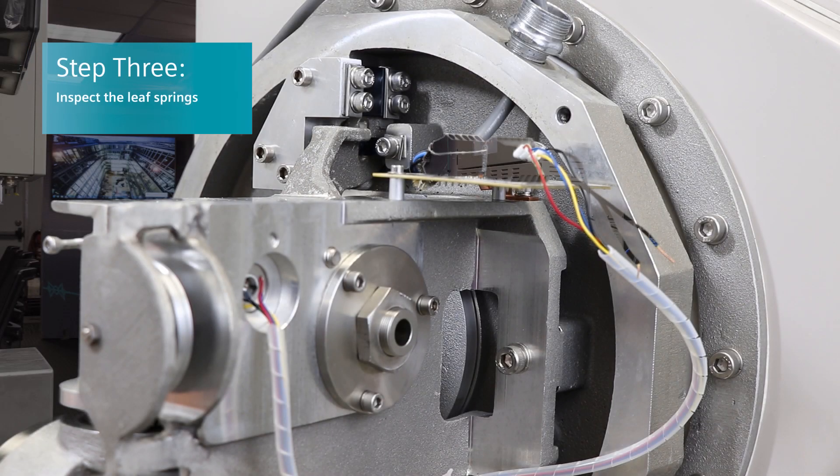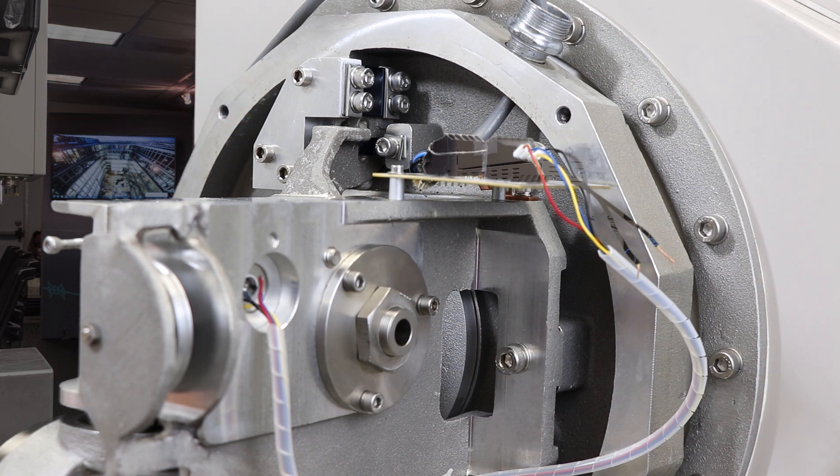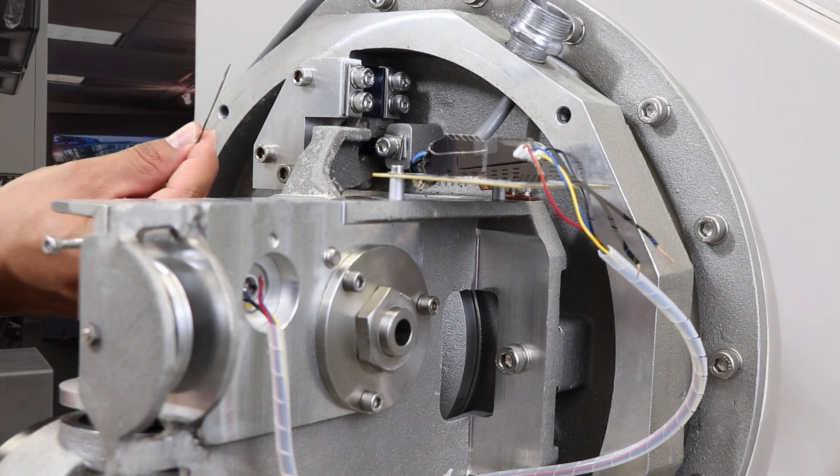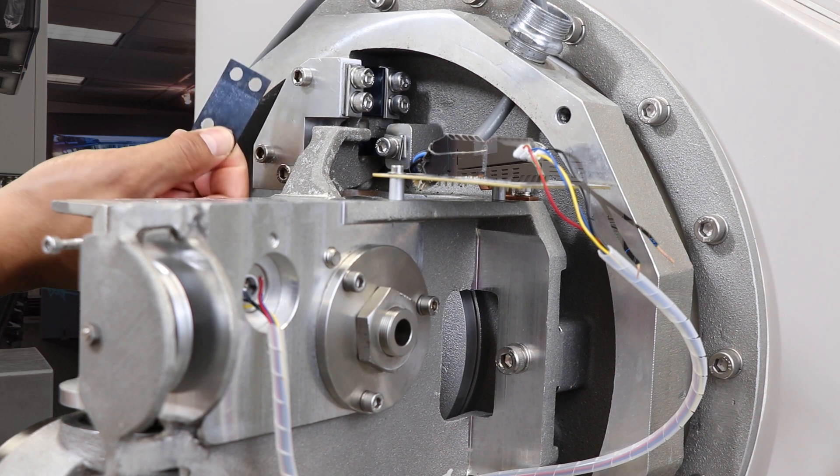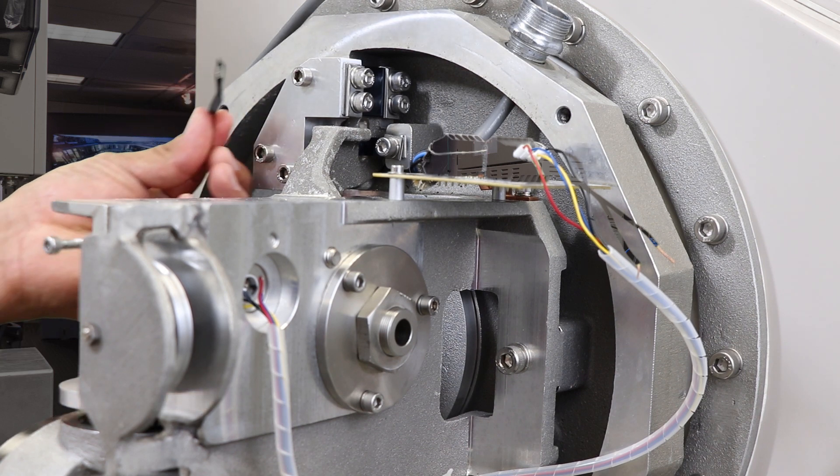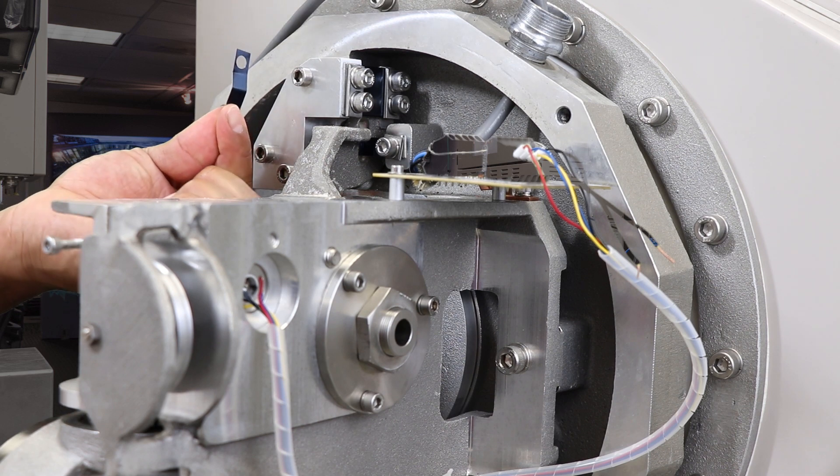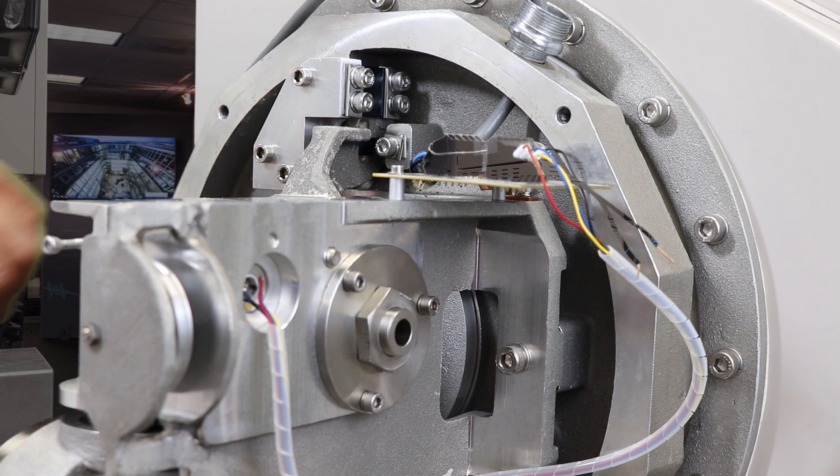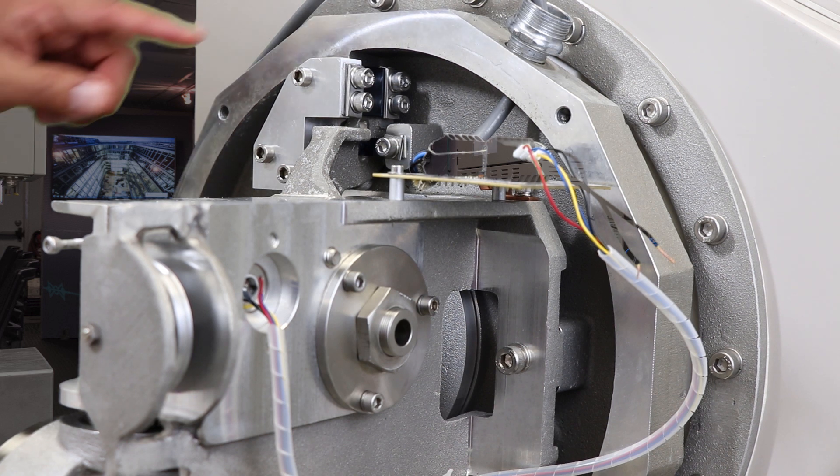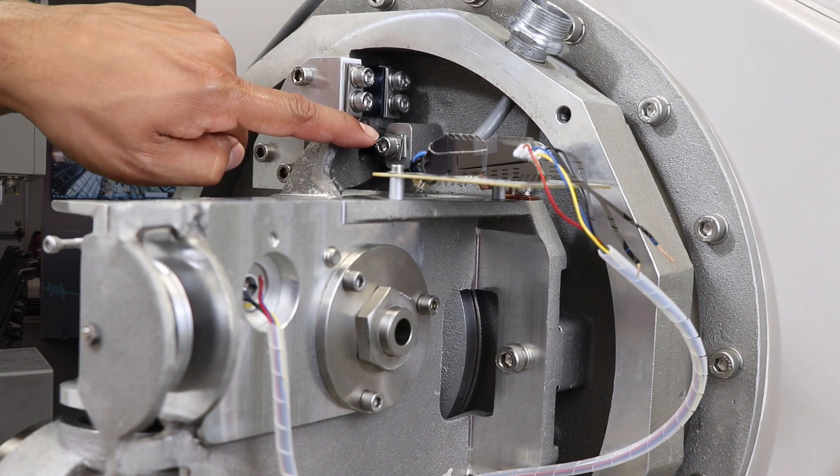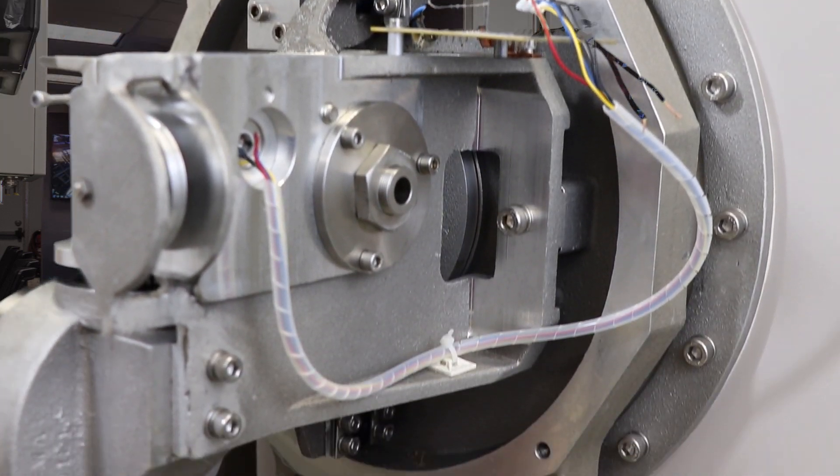Next we're going to inspect the leaf springs. The leaf springs should be flat and not bent. This one is what a leaf spring should look like versus one that is bent. If one or more are bent, you need to replace them. There are four leaf springs, two at the bottom.